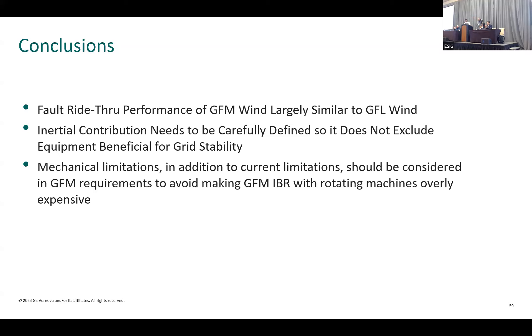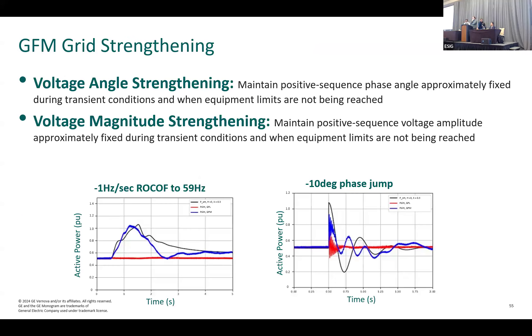Thanks Ignacio. A quick question: in some slides you mentioned a state-of-the-art GFL. We've heard a lot about inertia-based fast frequency response techniques, especially for type three, extracting energy from the rotating machine and putting it into the network. Is that enabled in these graphs? No, that's not enabled — we don't have that fast frequency response. It usually requires a fast PLL which creates a loop we are trying to avoid. So no, it's not included.